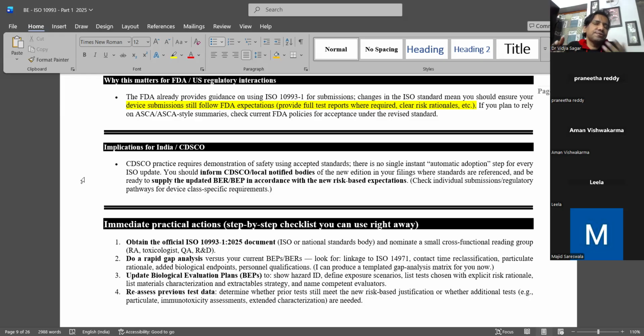Okay, but there you need to show a lot of proof on material and chemical characterization, and mostly do a lot of leachable and extractable studies in polar or non-polar solvents. You will have a different set of solvents, even a neutral solvent, to see whether it's extracting the leachables. A few tests can be done, mainly extractables, leachables, and chemical characterization. Then you can give a good justification. I have done it 2-3 times and passed it.